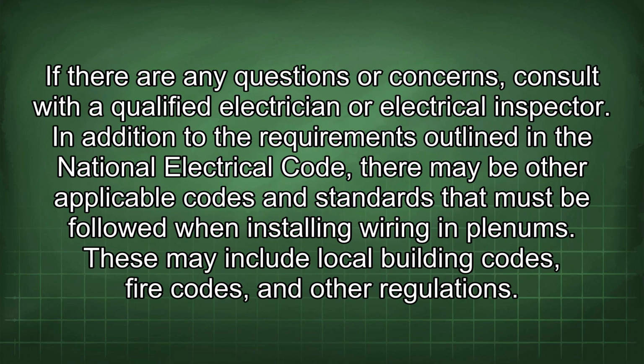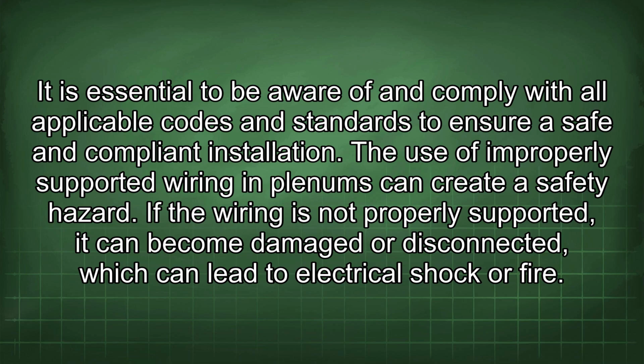If there are any questions or concerns, consult with a qualified electrician or electrical inspector. In addition to the requirements outlined in the National Electrical Code, there may be other applicable codes and standards that must be followed when installing wiring in plenums. These may include local building codes, fire codes, and other regulations. It is essential to be aware of and comply with all applicable codes and standards to ensure a safe and compliant installation. The use of improperly supported wiring in plenums can create a safety hazard. If the wiring is not properly supported, it can become damaged or disconnected, which can lead to electrical shock or fire.